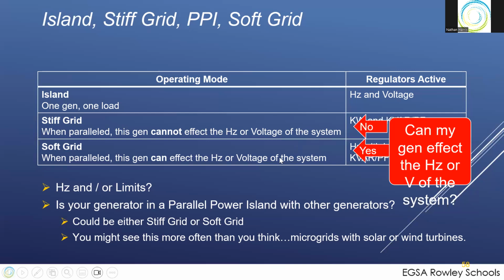If it's going to be a soft grid, you should have frequency limits in there so that you can't push past that point. Or make sure you set the mode properly, not as a generator in parallel with utility, but the mode would be generators in a parallel power island. You became the utility when they closed those breakers onto that grid on that island. So instead of being a KW regulated, this should have been a speed regulated system at that point.